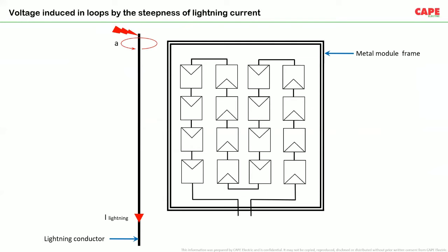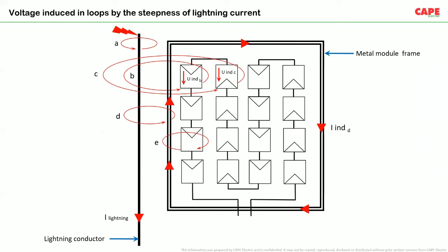One subject which you should always keep in mind is inrush current, probably a lightning current, or any current having a large di/dt, that means the rate of change of current is high, which may induce voltages into the module and the array, and this may damage the insulation of your PV modules or PV array. We have to be very careful. Probably the lightning is 1 kilometer away, but that lightning can induce voltage into your system if the system wiring is not carried out properly.